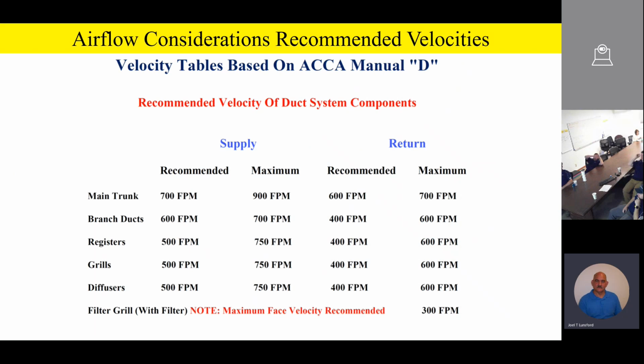Well, these are some velocity tables right out of Manual D, and we're going to recommend that you always follow ACCA Manual D. That's your airflow and duct design criteria. This velocity table is just a reminder to everyone that when we're building a duct system, we want to make sure our velocities are right in line as well, not only the total CFM, but also the speed or the velocity of the air.